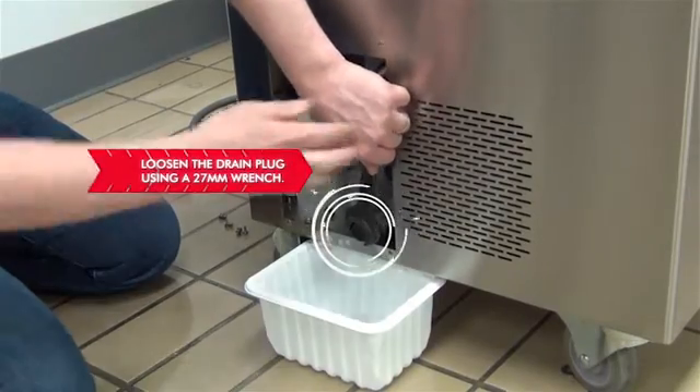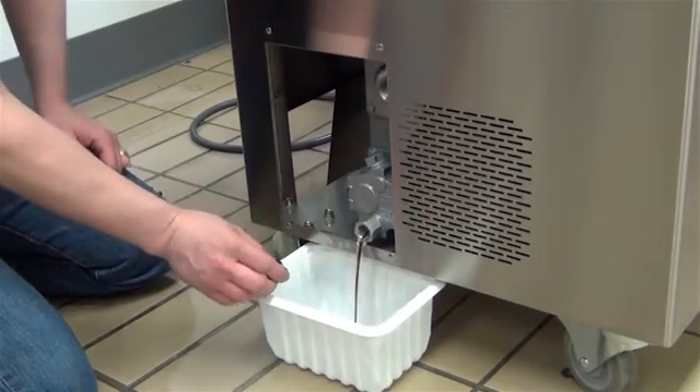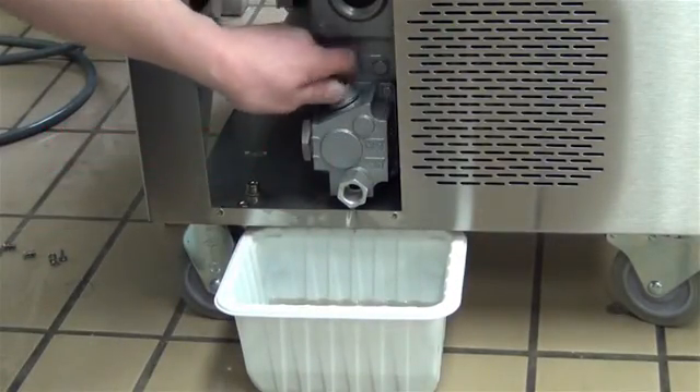Place a drain pan below the drain spigot on the side of the machine. Slowly loosen the drain plug using a 27mm wrench, or crescent wrench if necessary. Remove the oil fill cap using a 27mm wrench to allow all of the used oil to drain.